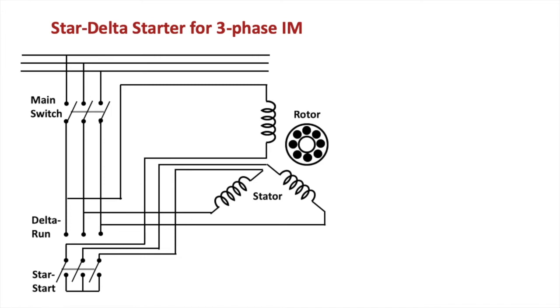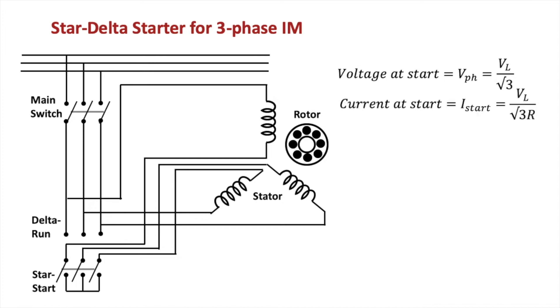So what is the advantage of connecting the motor in the star connection? When you connect it in the star connection, the voltage at the start will reduce to 1 by root 3 times of the line voltage. So if the voltage reduces, the current at the start is also reduced by root 3 times. So you are reducing the starting current with the help of the reduction in the voltage by changing the connection from delta to star. Because torque is proportional to V square, the torque produced at start will be only T by 3, that is, the torque at start will be reduced by 3 times the normal torque.